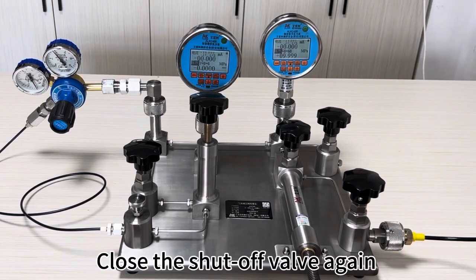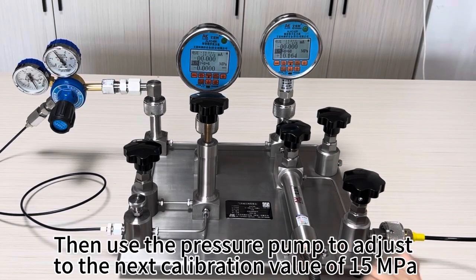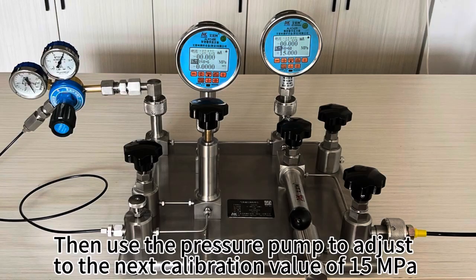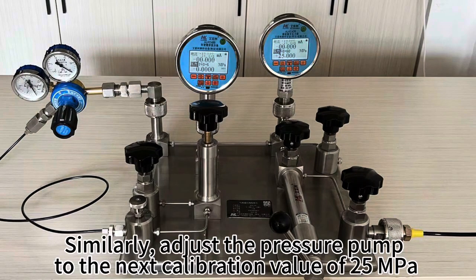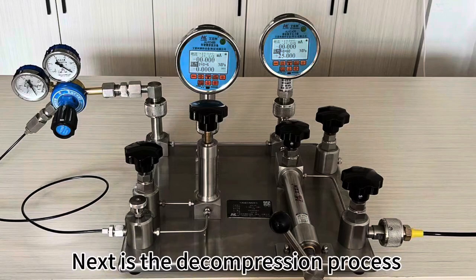Close the shut-off valve again. Then use the pressure pump to adjust to the next calibration value of 15 MPa. Similarly, adjust the pressure pump to the next calibration value of 25 MPa. Next is the decompression process.